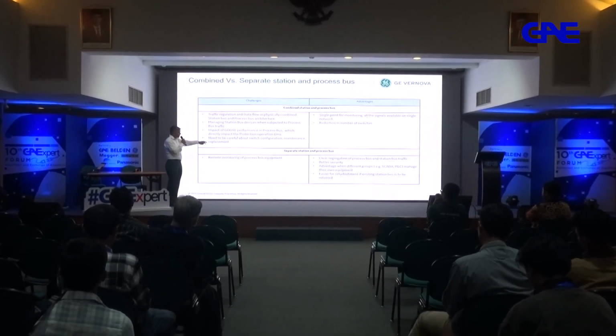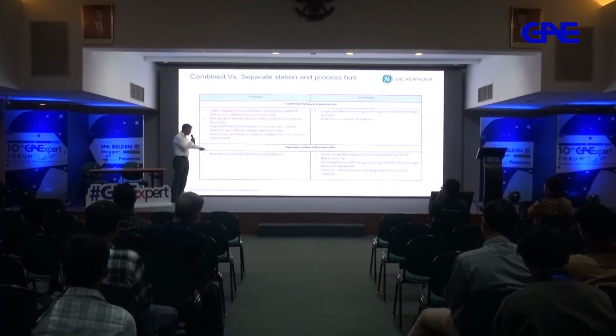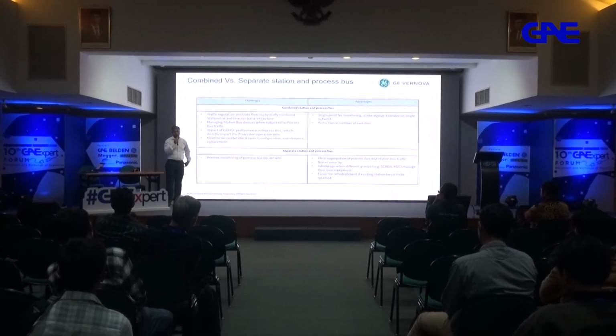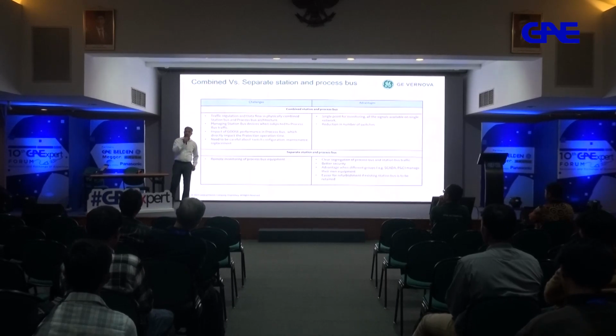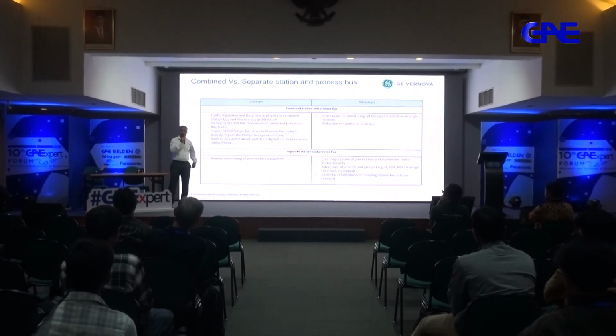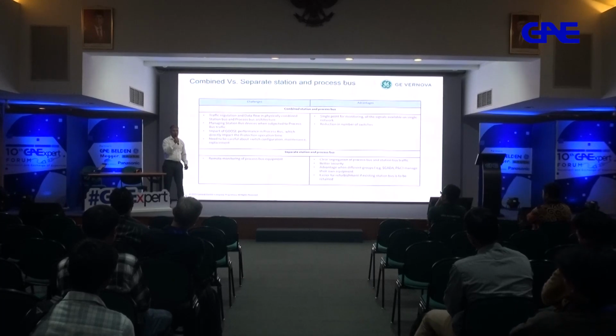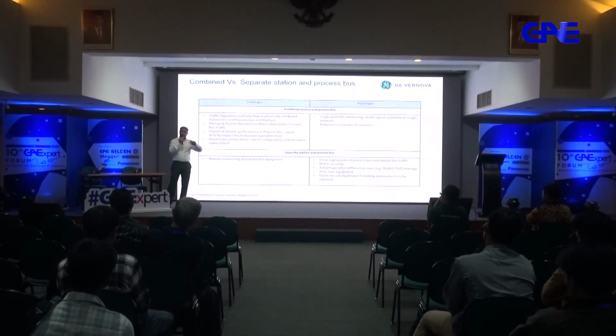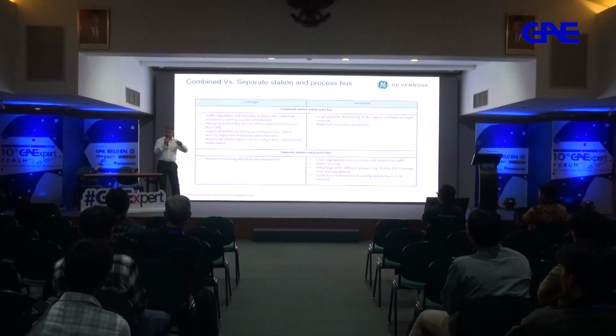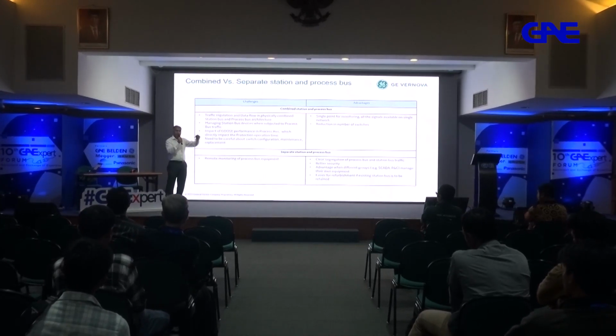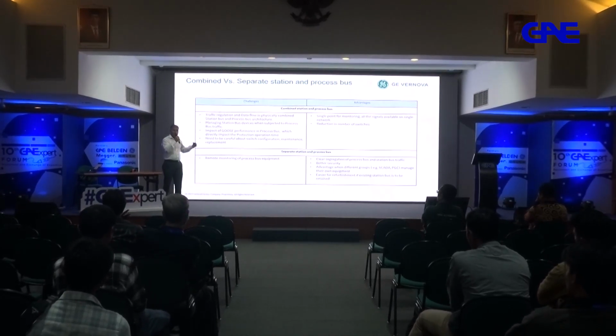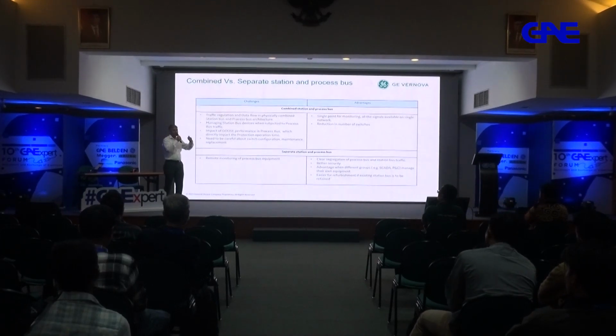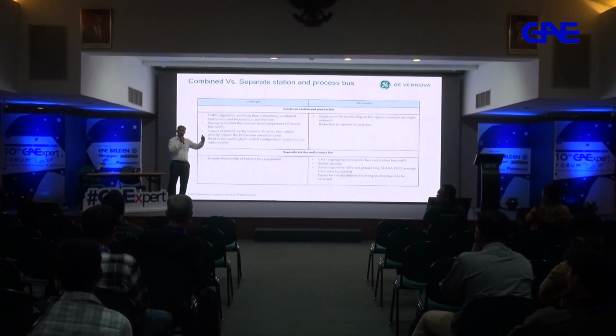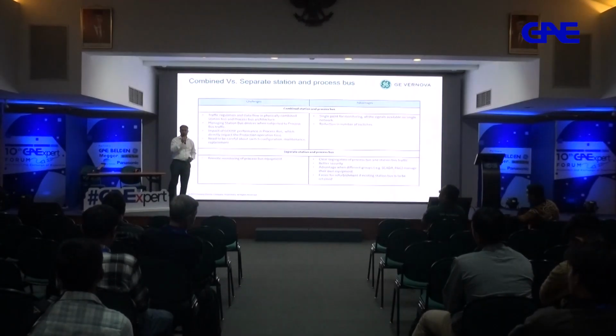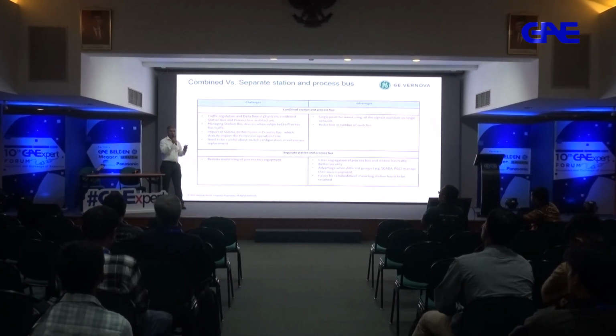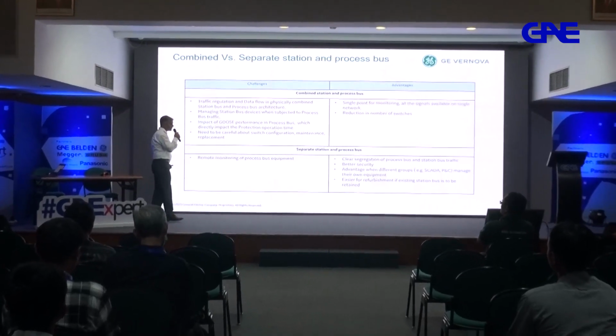For separate station and process bus, the challenge is remote monitoring of process bus equipment. If you want to monitor a merging unit from HMI, it's a challenge. In that case, you need to use the relay, the IED, as a proxy to monitor the merging unit. The merging unit should be able to send health data to the relay, and from the relay you can monitor the health in HMI. That can be done, but it's a bit of a convoluted process.